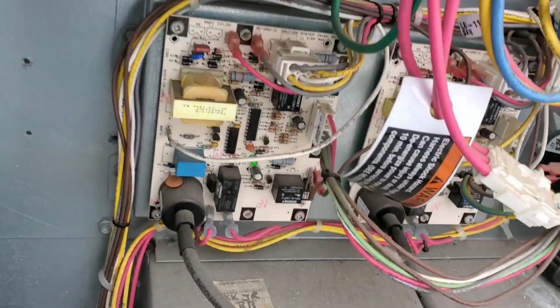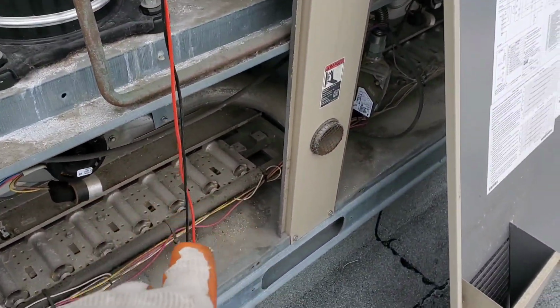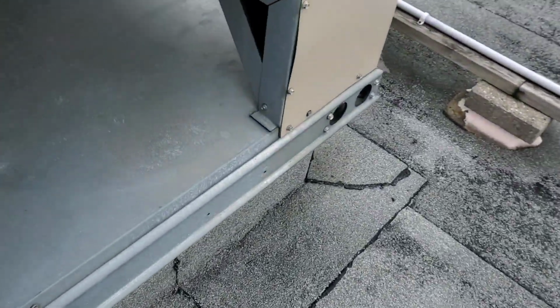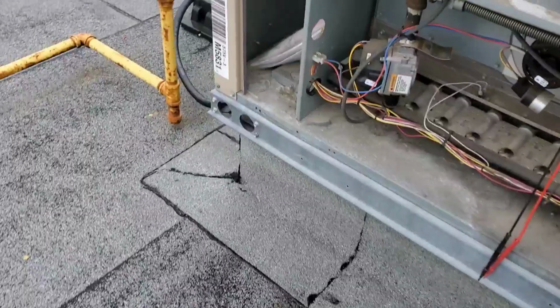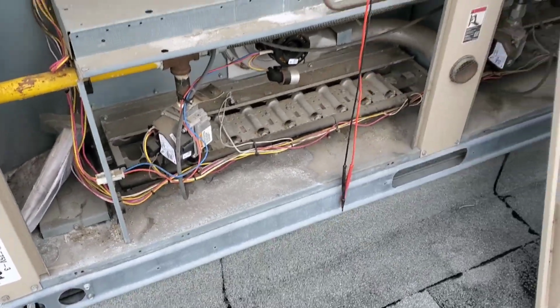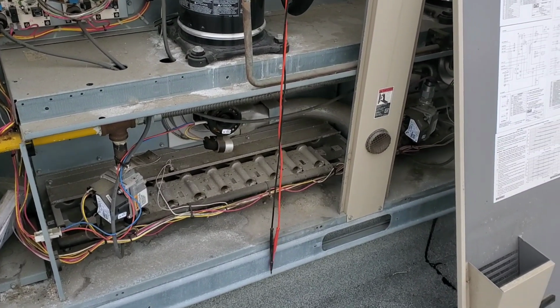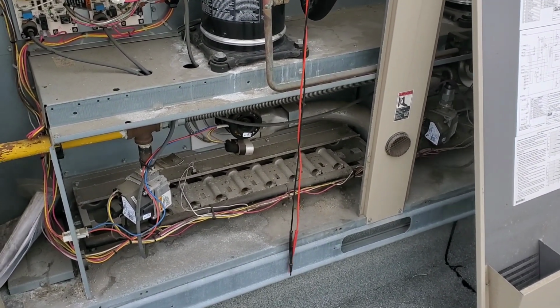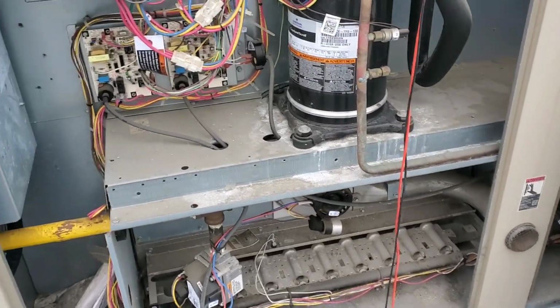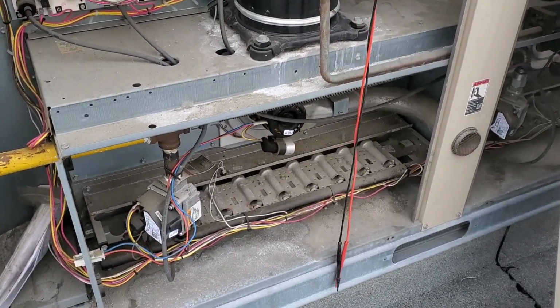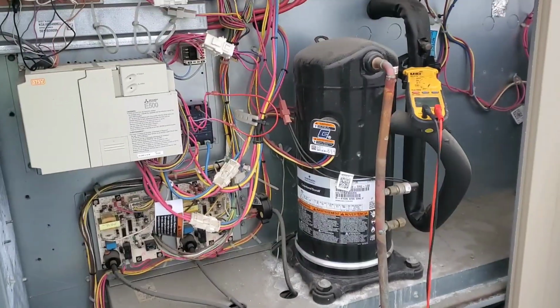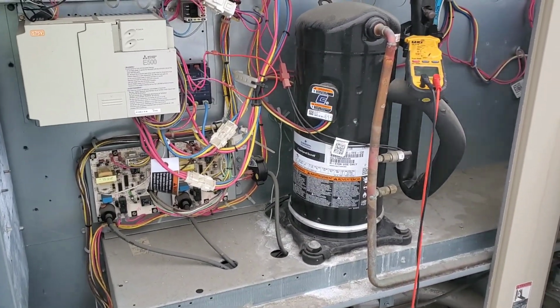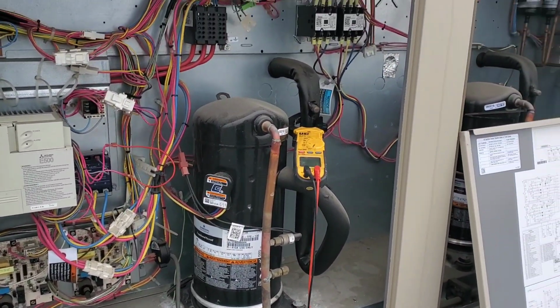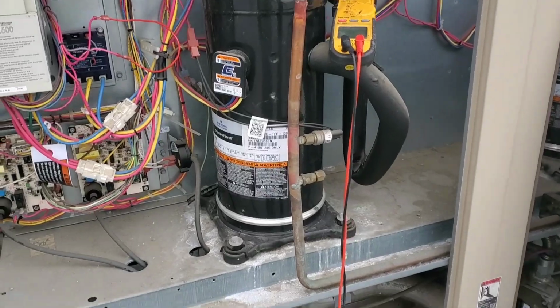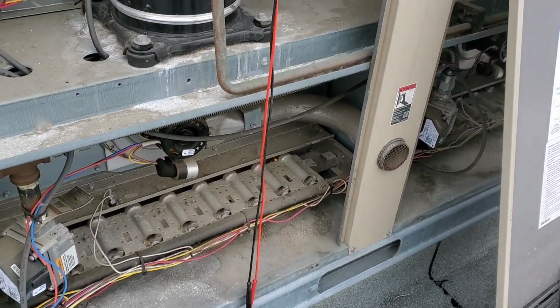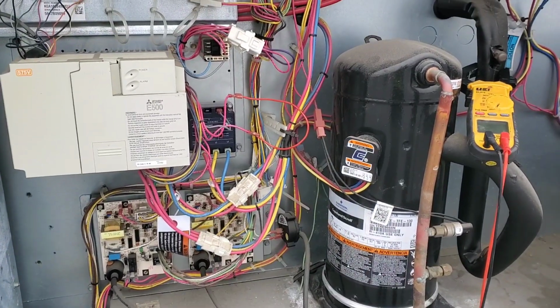Okay, we have power here. Blower motors running. Yeah, both blower motors running. We can usually jump this device, but this is not expensive, as I earlier said. We're gonna replace it. Just testing it without the device. So most of the units are without the device, but usually they put it for the bigger unit, like it's a 10-ton unit. So okay, so it's firing. Okay, so we're gonna replace it and test it again.